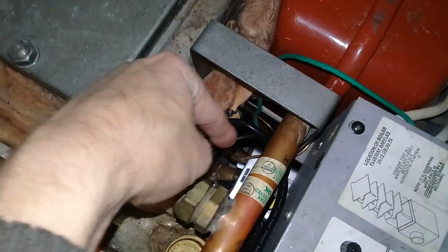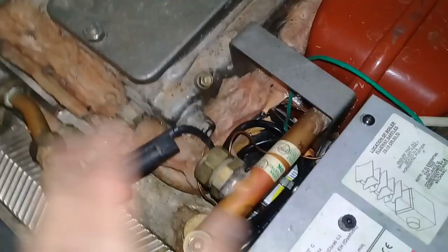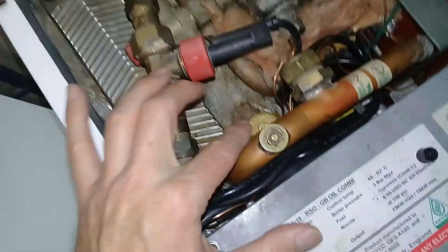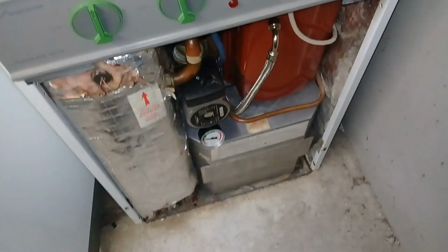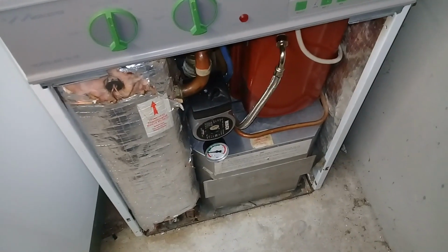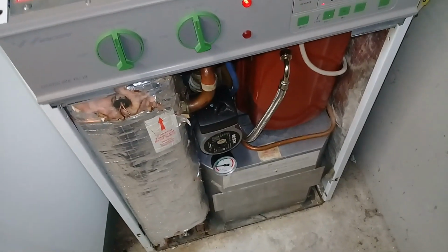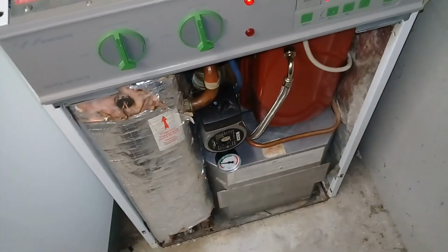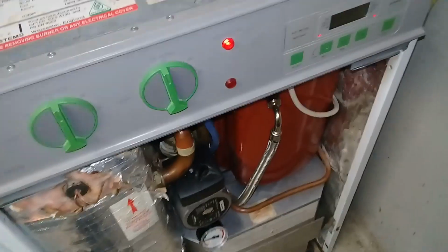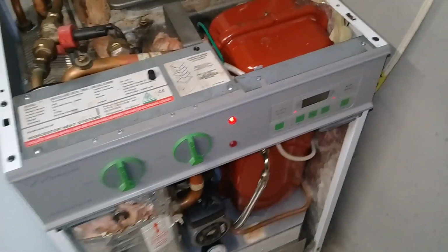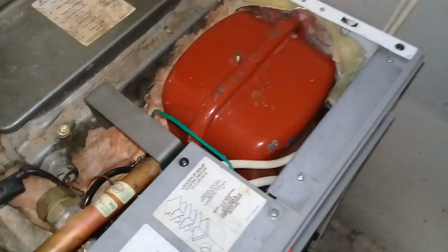bring the boiler back up to pressure, do all the bleeding techniques that I told you about earlier, getting the three-way valve in that mid position, lock position for central heating and water, running it on water heating, and then just bleeding from this one mainly, but I'll also be doing that one at the back and that one there. You're not touching the burner at all. When I do things on here, I typically turn the boiler off, but I'm just draining down and doing the simple stuff, not touching the burner and things like that. So yeah, that's what has been going on with this one.